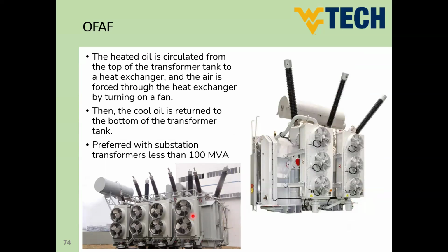A third type is oil forced air forced. The heated oil is circulated from the top of the transformer tank to the heat exchanger. Here we have the heat exchanger, and the air is forced through the heat exchanger by turning on a fan. Then the cool oil is returned to the bottom of the transformer tank. So in this case, guys, we have forced circulation for our oil through a heat exchanger. This is preferred, guys, with transformers less than 100 megavolt ampere. Okay, so this is oil forced air forced.